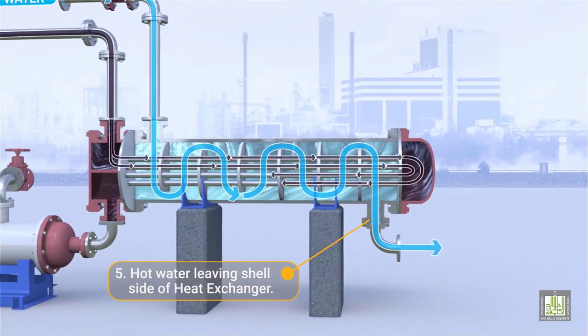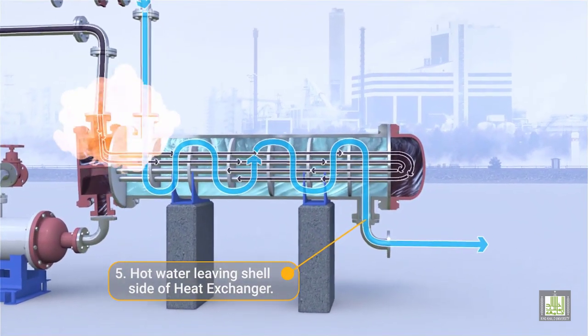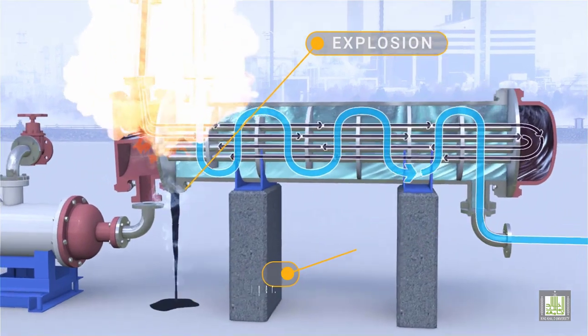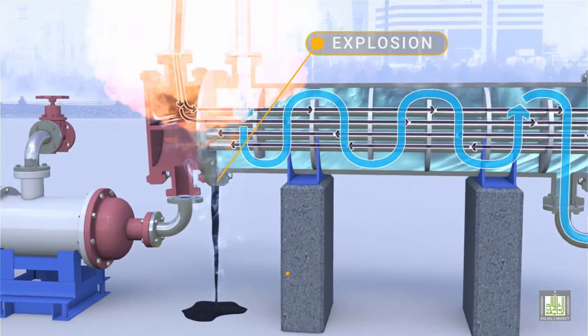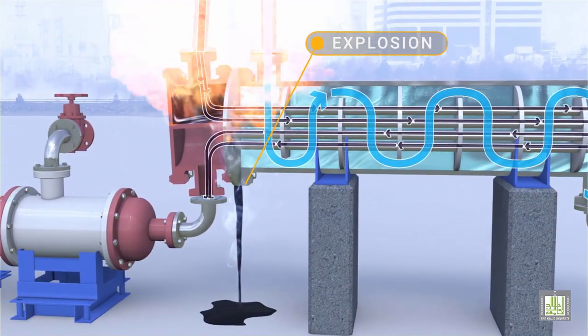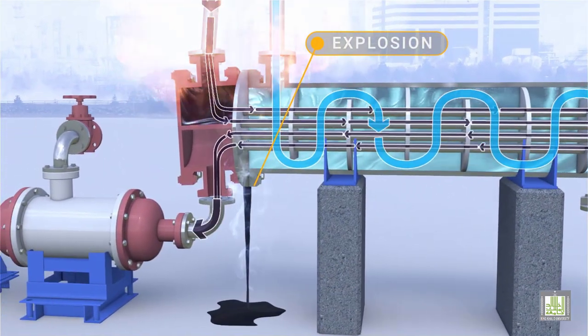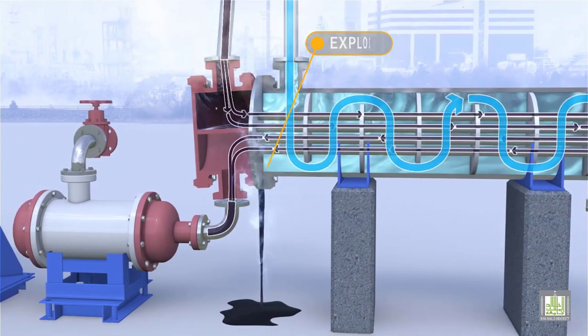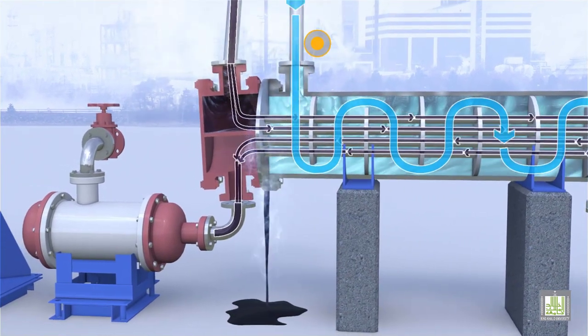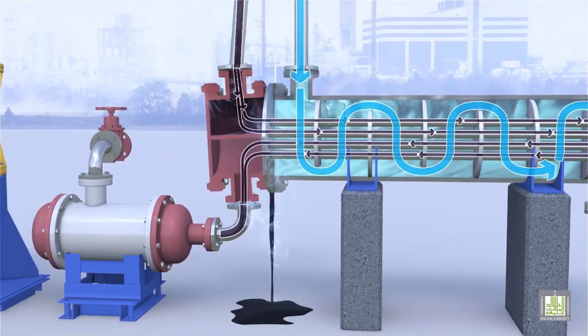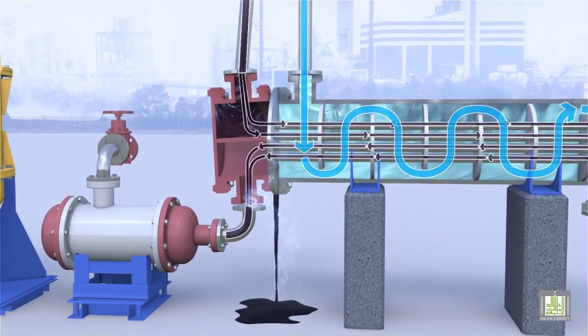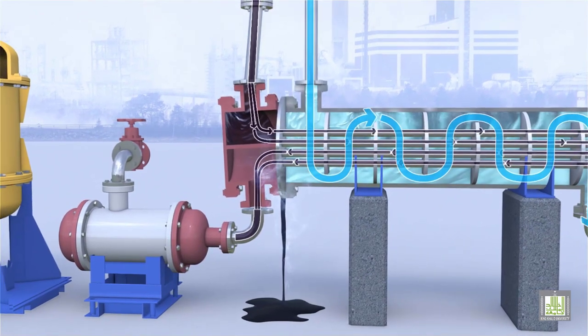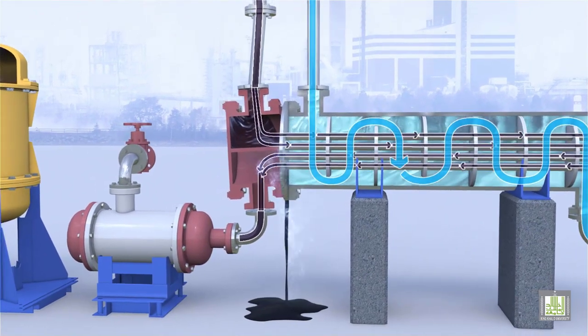The heat exchanger is typically provided with low or high point vents to remove water from tubes or the shell. Uncontrolled mixing of water with hydrocarbons can generate high pressure conditions and can damage systems that are not equipped with pressure relief devices.